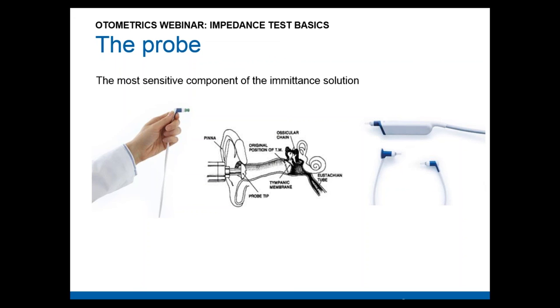Inside this probe we find a microphone, a receiver, and a pressure sensor — multiple important transducers miniaturized and introduced into an ear canal that can be very hot and warm with earwax. These conditions can affect the quality of the components, which is why the probe is the most sensitive part of the immittance solution. When choosing an immittance solution, the key questions are: what probe technology is used, how big is the probe, and how reliable is it?